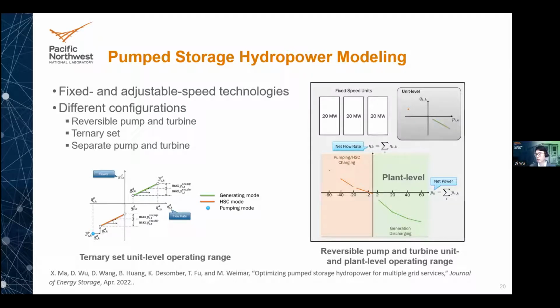In addition, the hydraulic short circuit at plant level helps increase the flexibility of system operation. This picture illustrates the operating power range versus flow rate in different modes for a ternary set at unit level. The picture on the right illustrates the unit and plant level operating range for fixed speed reversible pumps and turbines. As can be seen, although the fixed pumping power can only be realized at the unit level shown here, for the entire system, because of the plant level hydraulic short circuit, we have increased operating range in the pumping mode as shown here.